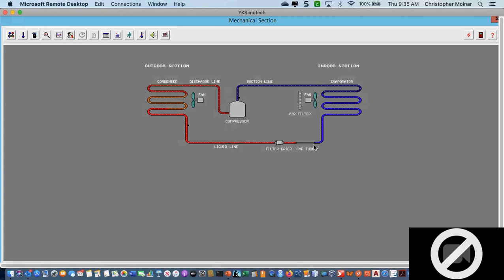Coming out of the cap tube, we call it a flash gas — basically a low-pressure spray of refrigerant, a combination of gas and liquid. It comes out of the cap tube, gets sprayed into the evaporator, where as it absorbs heat it boils off. That steam or vapor travels back to the compressor. Any time I boil a liquid and change it into a gas, I go through what's called a change of state — taking a liquid and changing it into a gas.